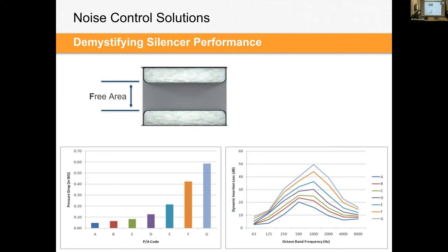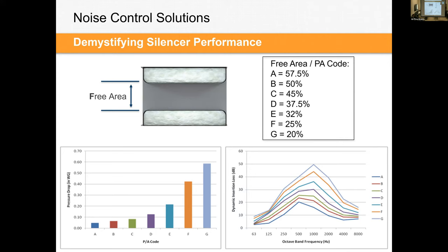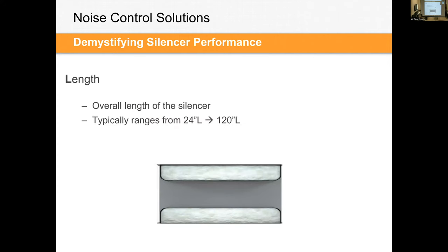As you close that gap, 57, 50, 45, 37 and a half, 32, 25, 20, your pressure drop goes up kind of exponentially, you can see, but your insertion loss also goes up. So by playing with that free area, going from A to G, you've got a very wide range of options to suit your needs. Depending on your airflow, your duct size, your construction, you can pick your best gap code. Does that make sense? It's a bit of a convoluted sort of mystical code that we use, but that's the science behind it. And I hope you guys leave with a better understanding of it. We'll also have all these slides available if anybody needs or wants. Don't feel like you need to memorize this, unless you want to.